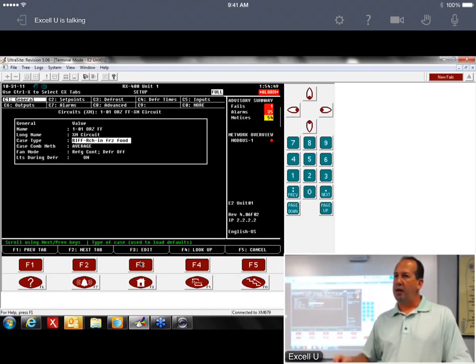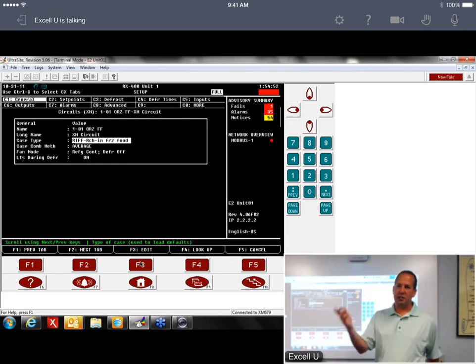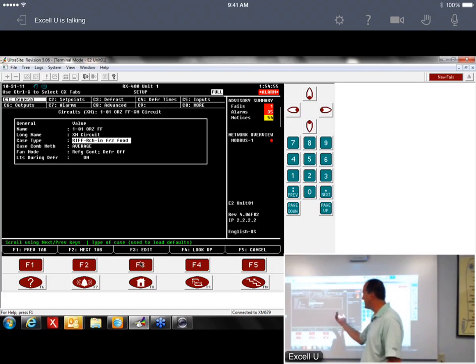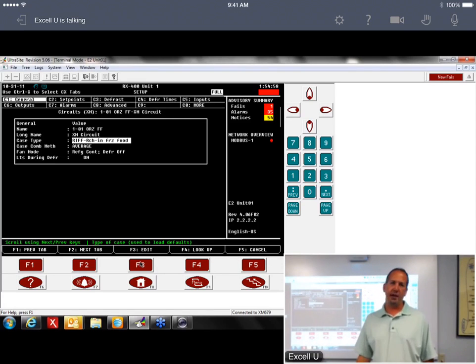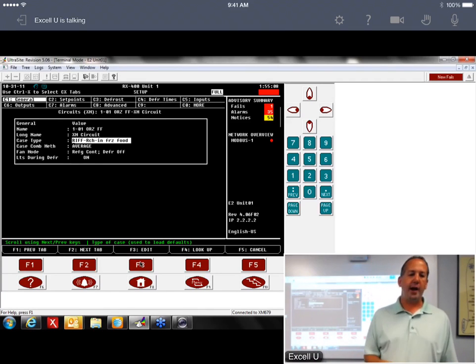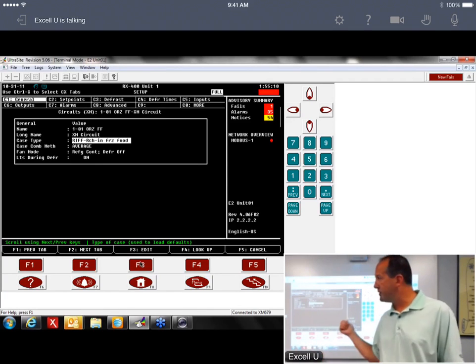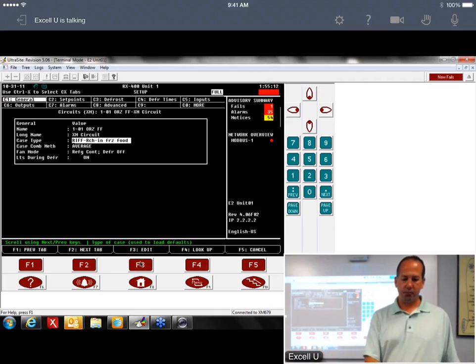And then after you put the case type in, you can change the parameters to whatever Hill Phoenix wants it to be. Let's say you put reach in frozen food, we may default it at minus 9.4 degrees. Well, Hill Phoenix says no, we run it at minus 3 degrees or minus 4 degrees. So you can override the set points once you select that case type.